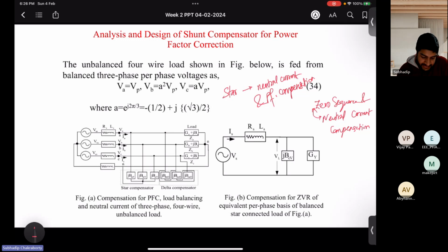So what will the delta compensator do? Anyone? For balancing the system. Load balancing. Yes, load balancing. Now, by the term load balancing, don't think neutral current compensation. Both will lead to load balancing, but when I term it as load balancing, neutral current compensation is already taken care of by the star. Load balancing means negative sequence compensation. The zero sequence neutral current is already compensated by the star. Load balancing means negative sequence currents will be compensated by the delta.